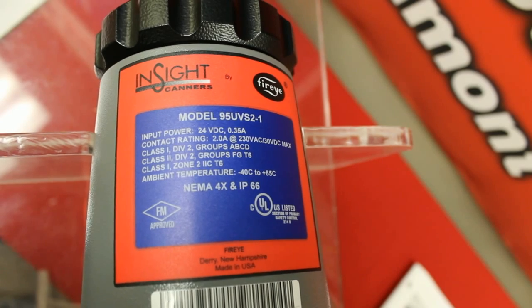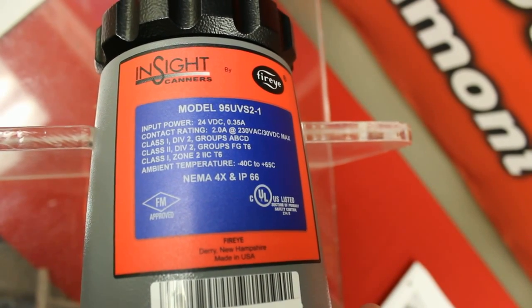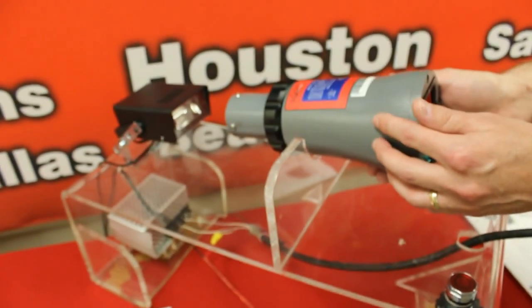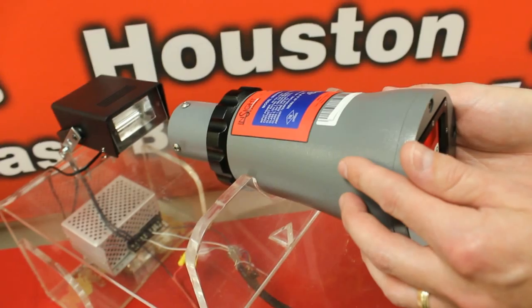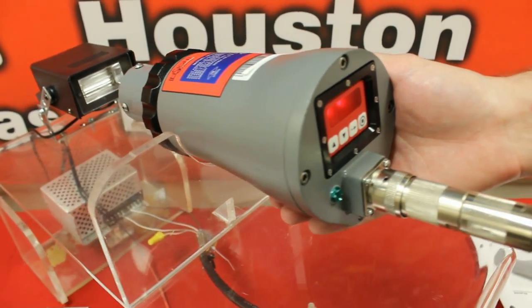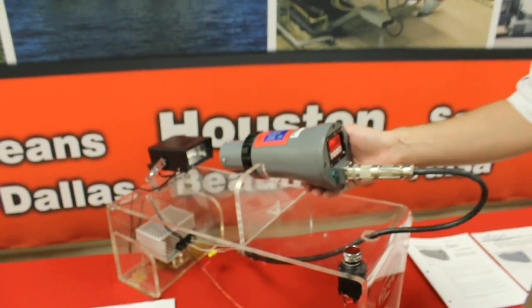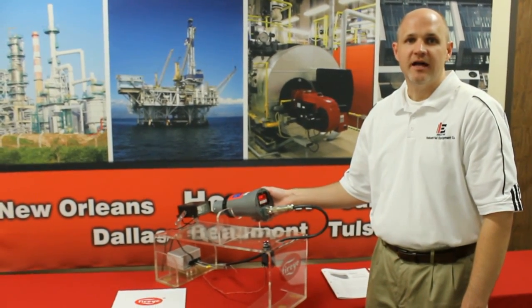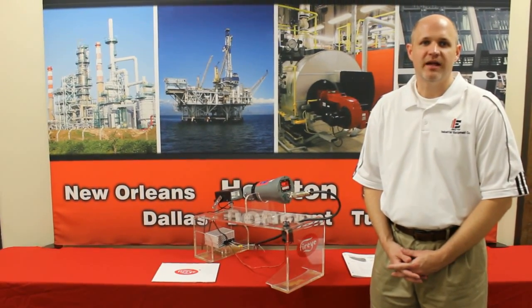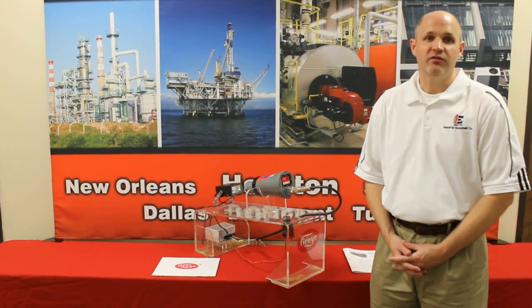This particular model is FireEye's Insight 95 series flame scanner. This model is 95UV-S2-1, which is a UV only flame scanner. This Insight flame scanner is also available in an IR only scanner, as well as a dual scanner using a combination of both UV and infrared. The dual type scanner in this series — that model number — is a 95DSS2-1. The FireEye Insight Type 95 series flame scanners are a microprocessor-based flame scanner utilizing solid state UV or IR, or a combination of both UV and infrared.